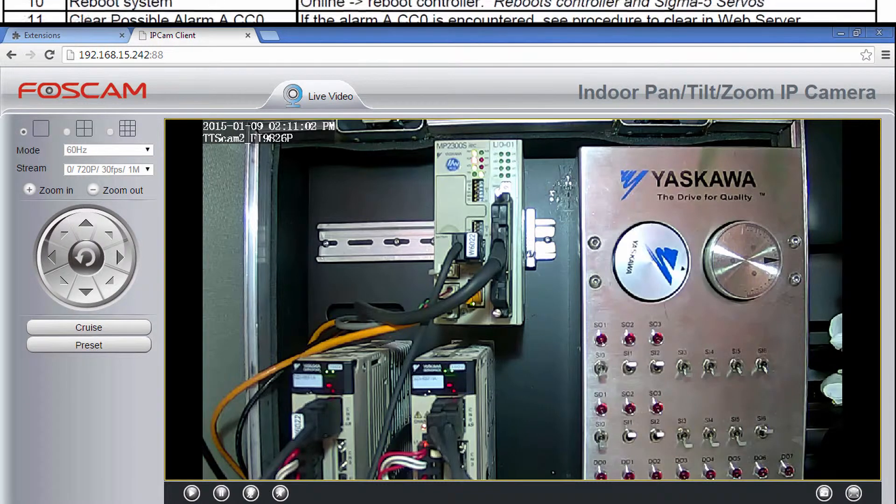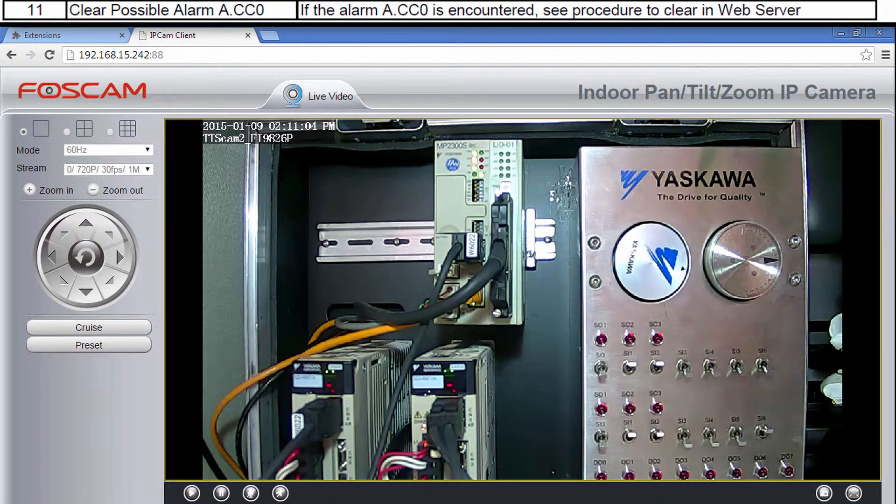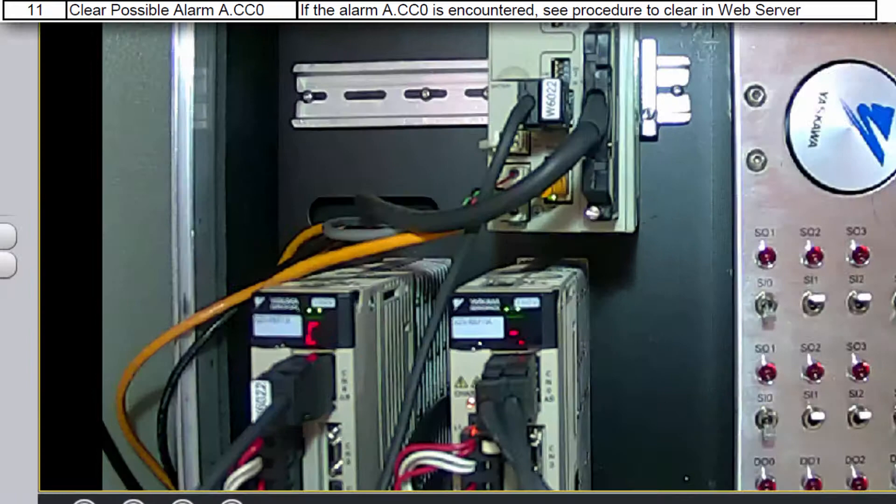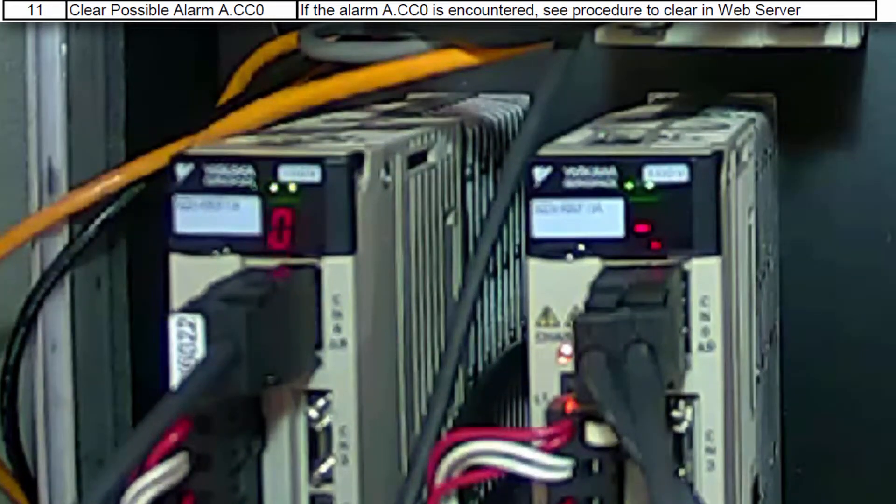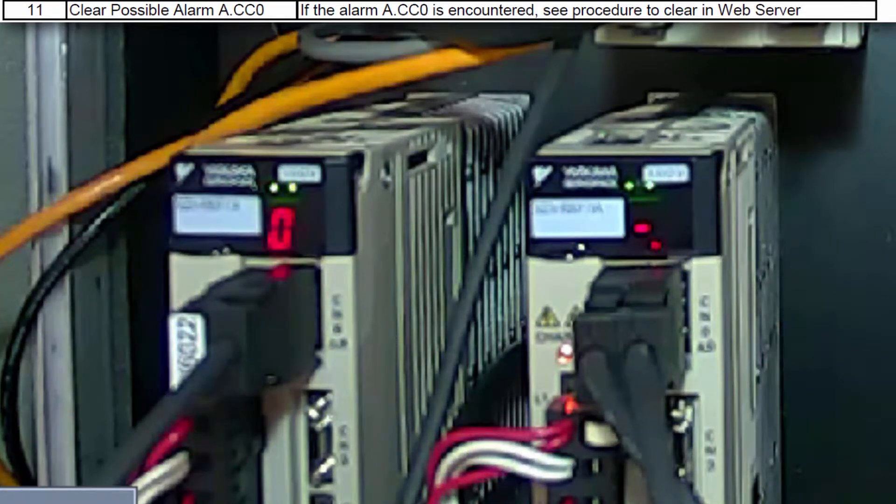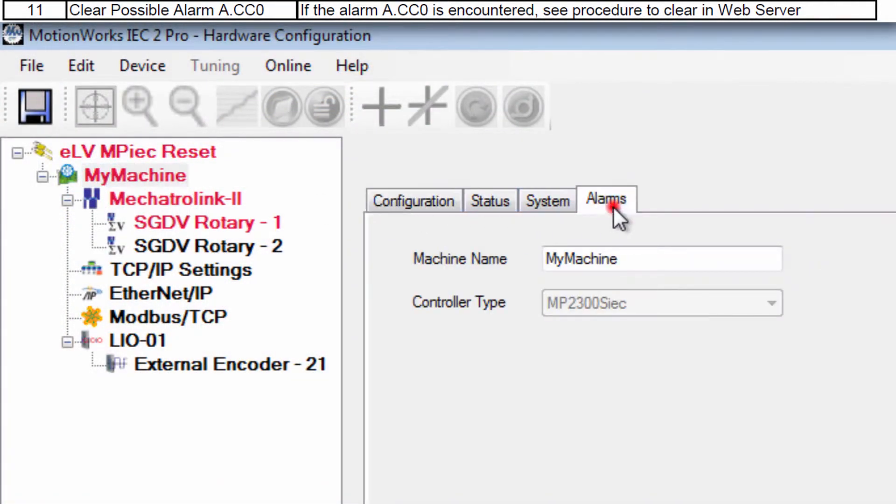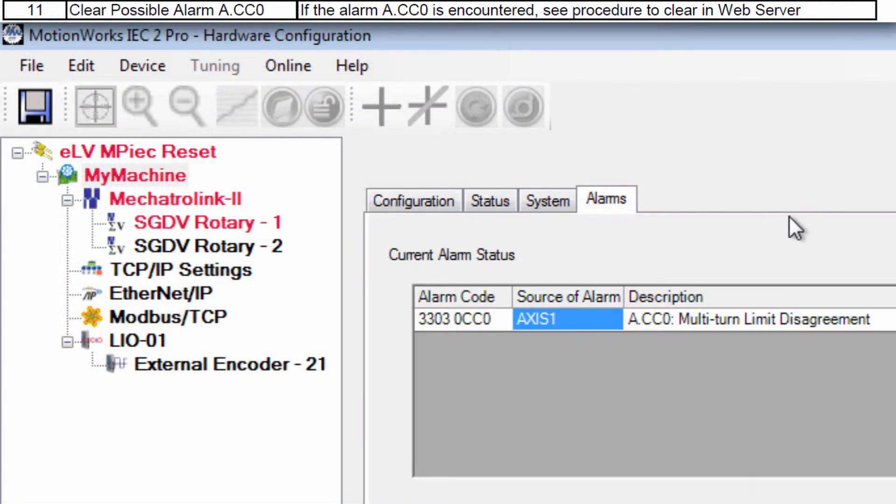But now as one final troubleshooting possibility if the motors are not new it is possible to get the A.CC0 alarm at this point and that comes from the multi-turn limit parameter which might still be stored in the encoder of the motor.